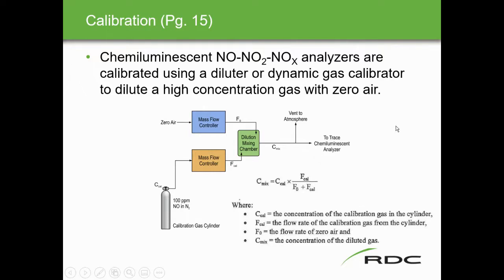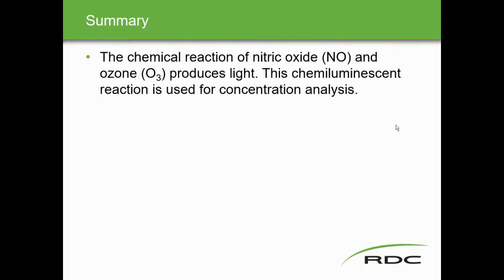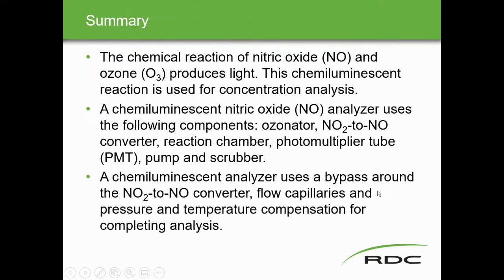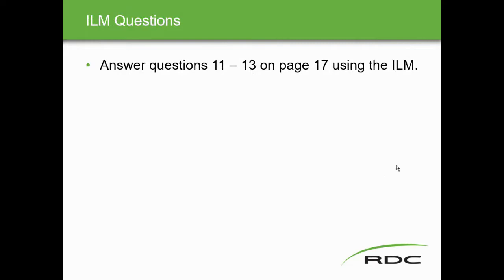Summary: the chemical reaction of nitric oxide and ozone produces light — this chemiluminescence reaction is used for concentration analysis. The chemiluminescent nitric oxide analyzer uses these key components: ozonator, NO2-to-NO converter, reaction chamber, photomultiplier tube, vacuum pump, and scrubber. By switching between NOx mode and NO mode and subtracting, we obtain the NO2 concentration.